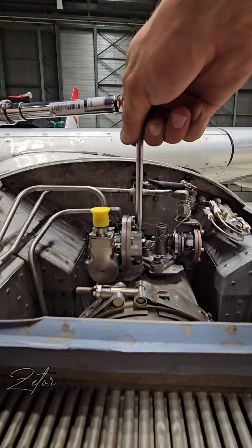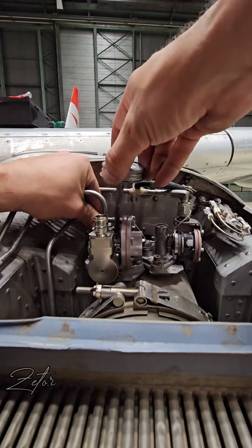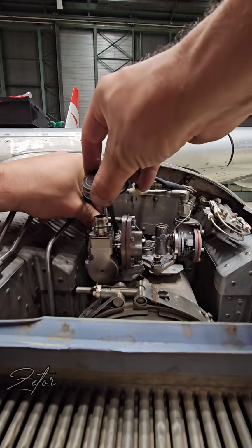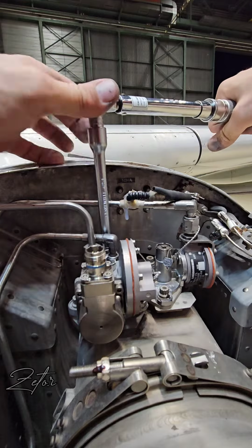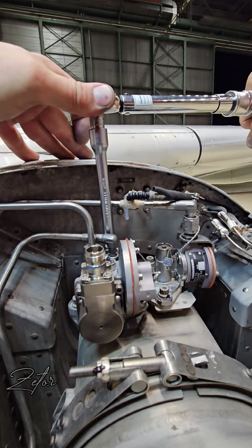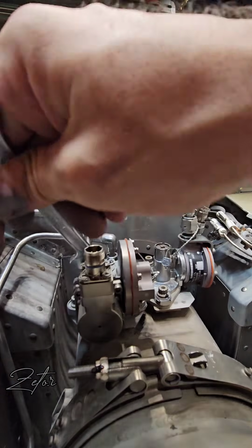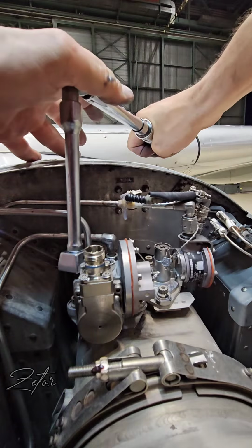The next case is overpressure. The PRV pneumatically regulates the bleed pressure around 44 psi, but when the pressure regulator transducer sends a pressure greater than 57 psi, the BMC will send the closing signal.